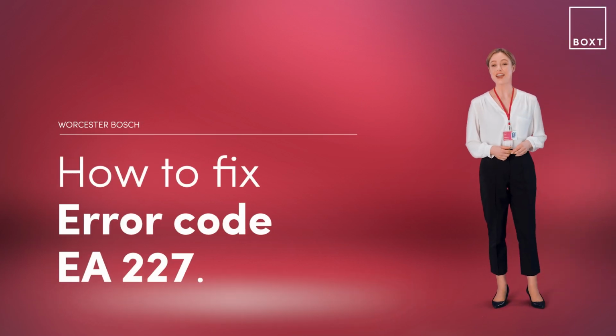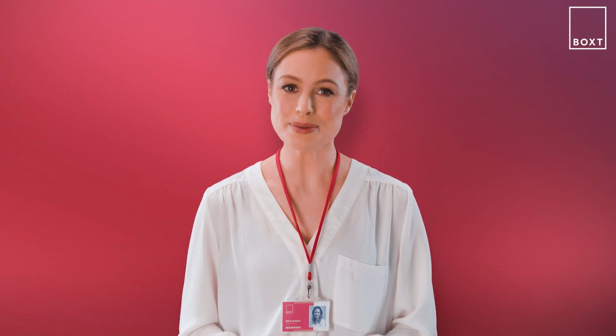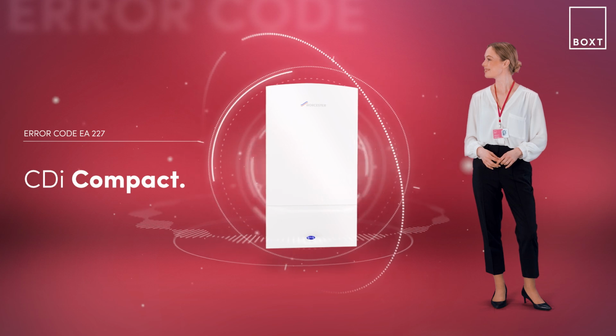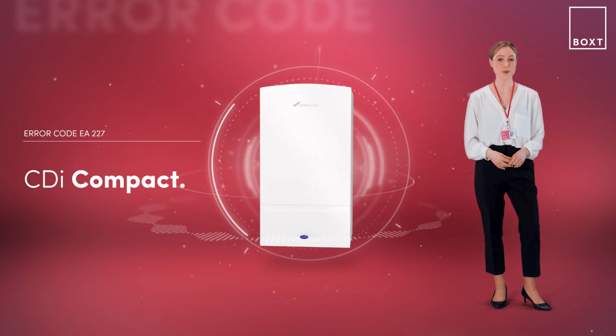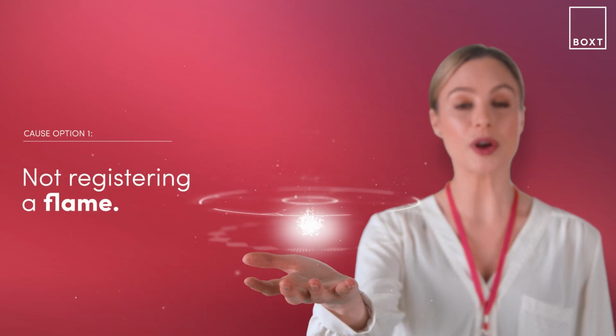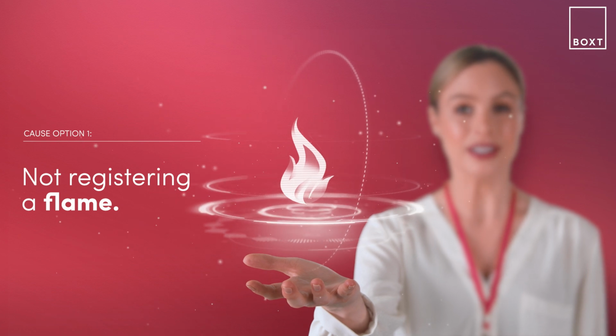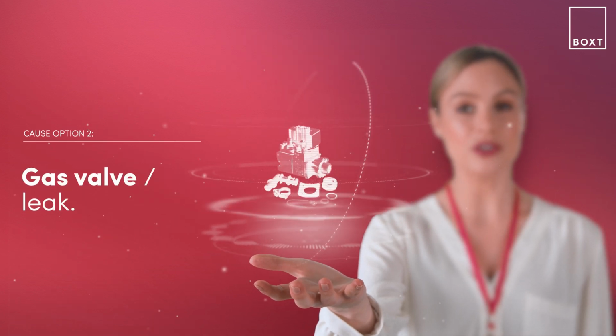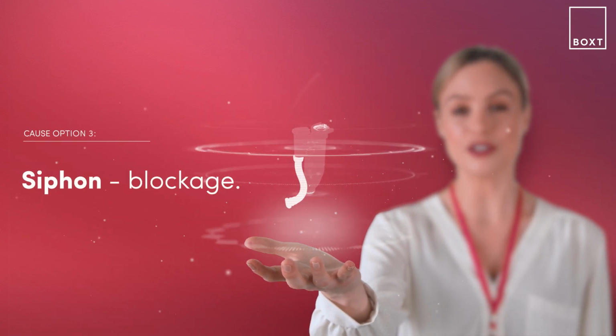This is how to fix the error code EA227 on your Worcester Bosch boiler. If it's displaying an error code, it simply means there's something wrong with your boiler. With the CDi Compact boiler, this problem is likely caused by your boiler not registering a flame. This could be an issue with the gas valve unit, or it could be a blockage in the siphon.